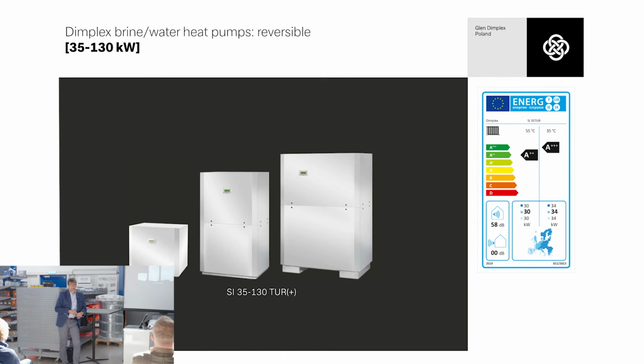And also we have one machine with an additional plus. This plus means that this machine is equipped with a second condenser, a second heat exchanger we can use for simultaneous production of heat during the cooling. So we can spread the waste heat directly, for example, to the domestic hot water cylinders or to swimming pools or some other purposes, for example, some production which needs some special energy, or maybe for ventilation which needs some warming up even during the summer.